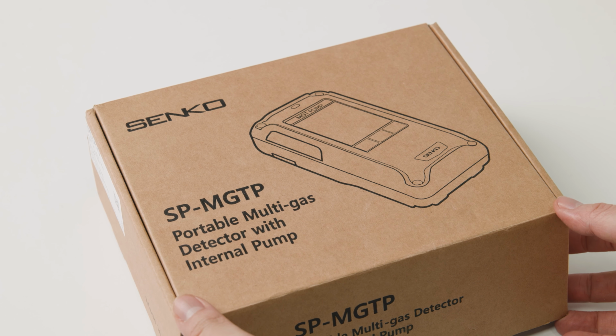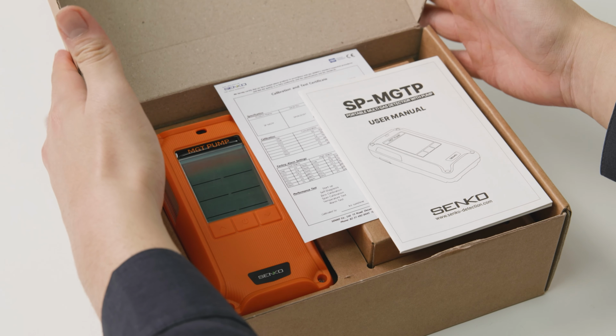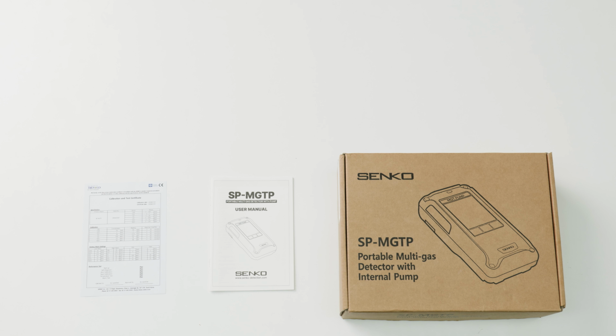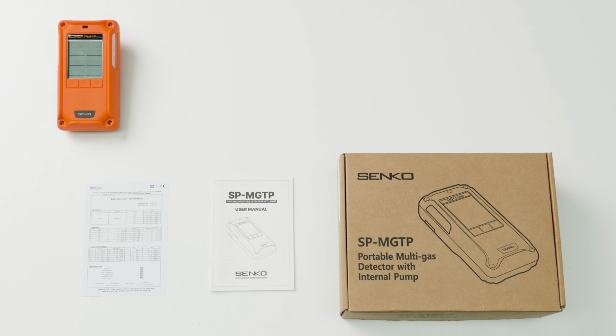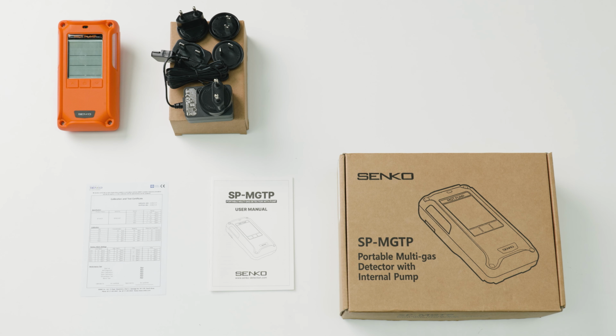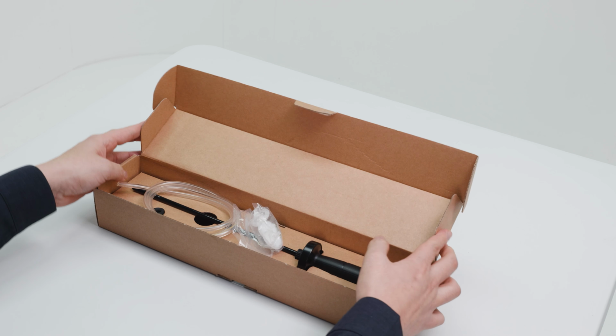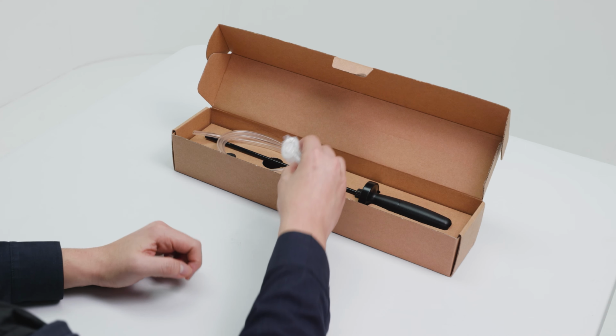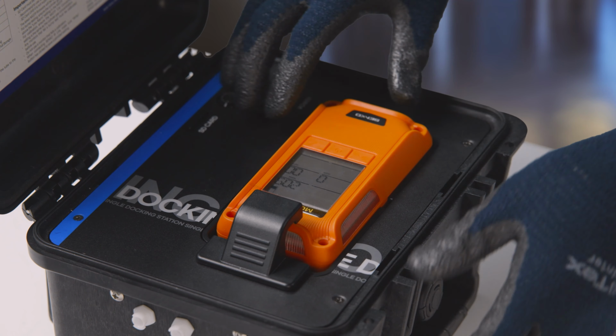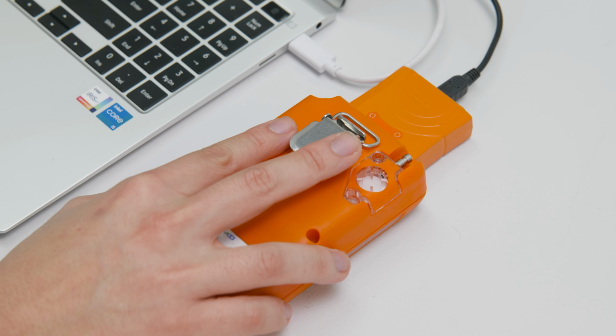Let's take a look at what's included in the SP-MGTP package. When you open the box, you will first find the calibration certificate, which confirms that the device was calibrated before shipment, along with the user manual. Underneath, you will find the SP-MGTP main unit and the charging adapter, with interchangeable plug heads to support different power standards around the world. The package also includes all the essential components for gas sampling, including 1 quick disconnector, 5 dust filters, 5 PTFE filters, and a 1-meter sampling tube, which are used for active gas sampling through the gas inlet. A range of optional accessories is also available. Items such as the sampling probe, docking station, and IR link can be purchased separately and connected as needed to expand the functionality of the SP-MGTP.